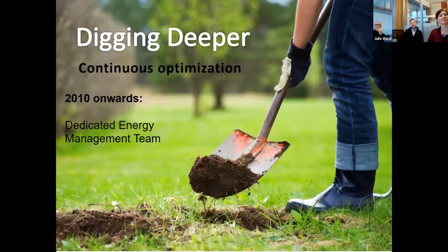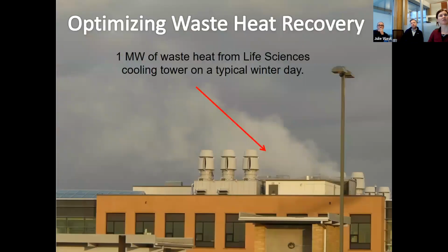Good one, Zach. So digging deeper, from 2010 onwards we had a dedicated energy management team. I think we had two people in energy management in 2020. And the first thing that was noticed is that the cooling tower was rejecting heat in the middle of the winter. Roughly 1 megawatt of waste heat from the life sciences cooling tower was rejected out of the building on a typical day. For those of you just looking into these things, if you have LEED buildings, they often have waste heat energy recovery from the cooling systems, and they often are not commissioned to work properly. So this is a really easy one to find. Is your cooling tower running in the middle of winter? Ask yourself that question and you will be very surprised at how often you're rejecting heat when you shouldn't be.